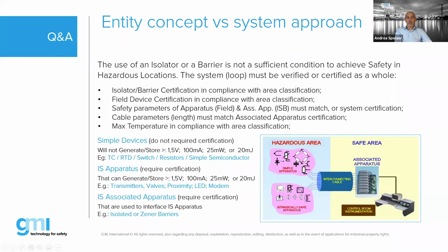Single components or some components cannot make the system intrinsically safe on their own. It is the complete system loop that needs to be considered as a whole. There's the system concept, where the entire system is assessed and certified as one unit, so in this case the system can be assessed safe. For instance, our multiplexer for zone 1 is a single unit for zone 1, but a single data acquisition device cannot be used with a master or gateway that is not ours. That's just an example, not specific to GMI, but illustrates that the system must be complete in order to be certified.